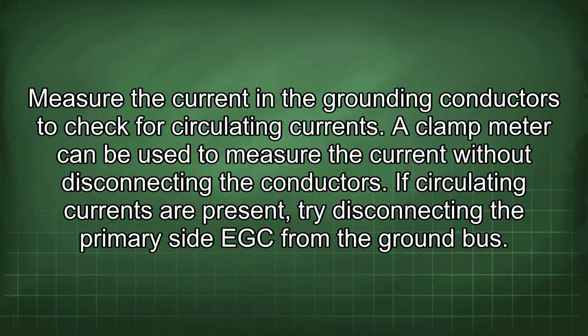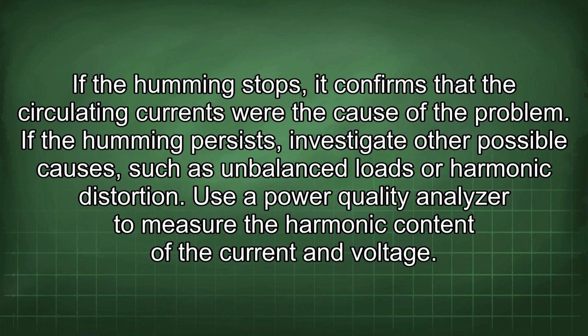Measure the current in the grounding conductors to check for circulating currents. A clamp meter can be used to measure the current without disconnecting the conductors. If circulating currents are present, try disconnecting the primary side EGC from the ground bus. If the humming stops, it confirms that the circulating currents were the cause of the problem. If the humming persists, investigate other possible causes such as unbalanced loads or harmonic distortion. Use a power quality analyzer to measure the harmonic content of the current and voltage.